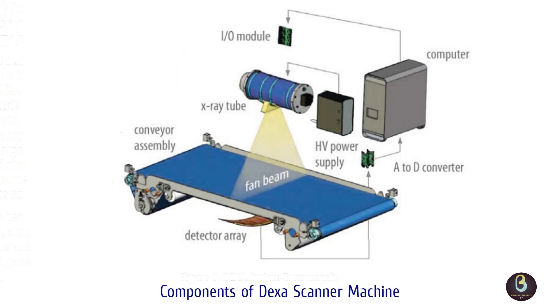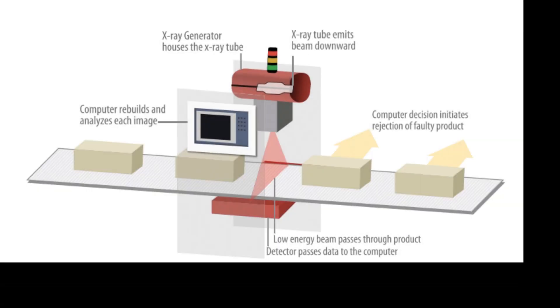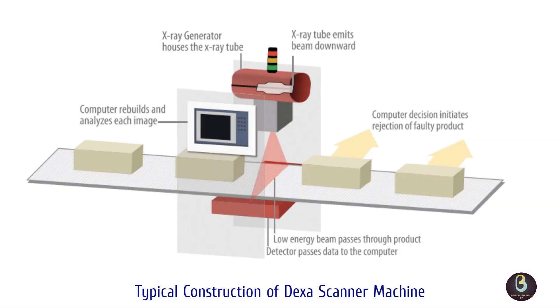The electrons are accelerated to the target by applying a high voltage between the anode and the cathode. When the electrons hit the tungsten target mounted inside the copper anode, they decelerate rapidly and this deceleration creates the X-ray emissions.